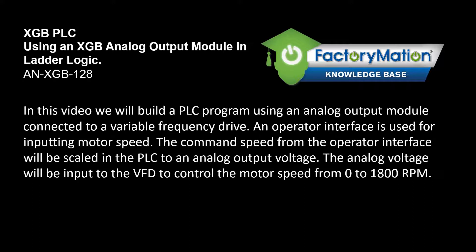In this video we will build a PLC program using an analog output module connected to a variable frequency drive. An operator interface is used for inputting motor speed. The command speed from the operator interface will be scaled in the PLC to an analog output voltage. The analog voltage will be input to the VFD to control the motor speed from 0 to 1800 RPM.